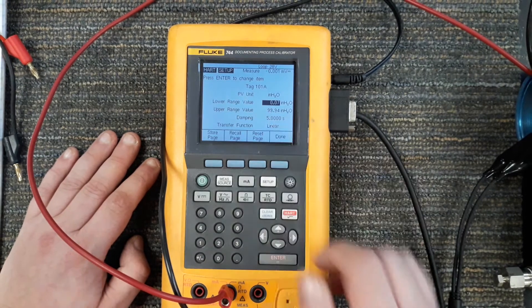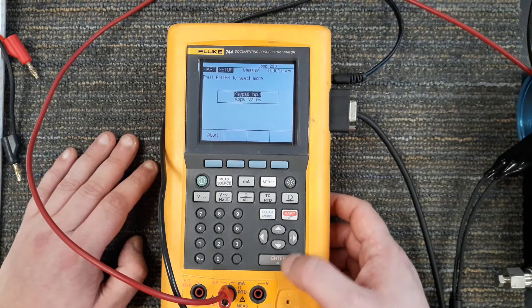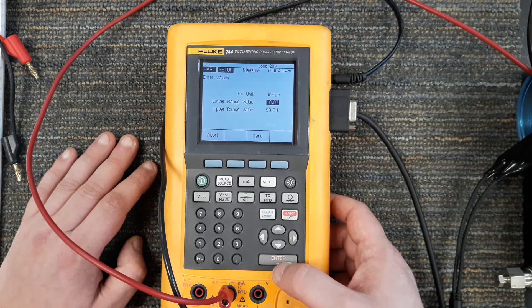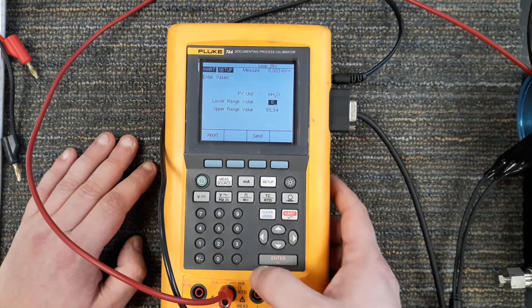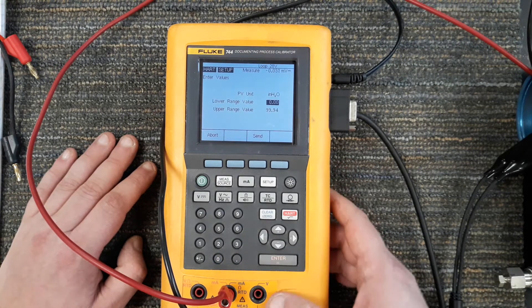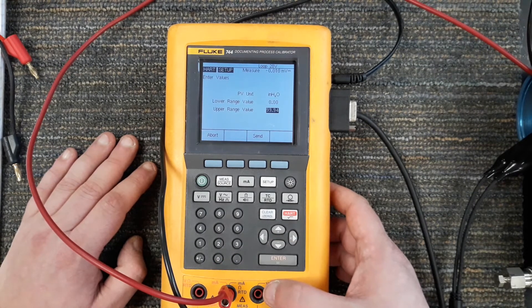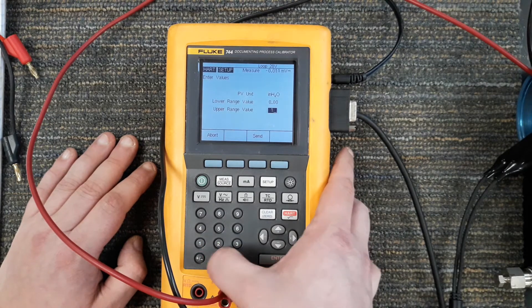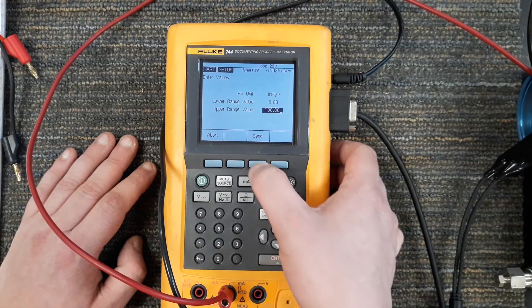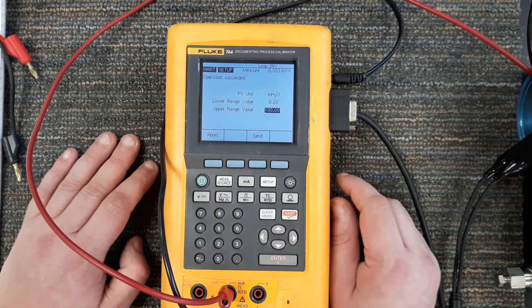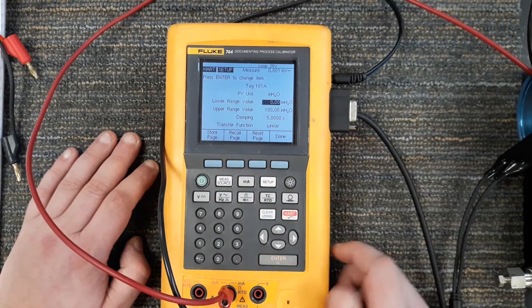Now these lower range values don't look quite right. Someone must have put these in, but I can set the lower range value to be exactly 0.00 and I can set the upper range value to be exactly 100.00. Hit send, continue, and now it's put those two values in there.